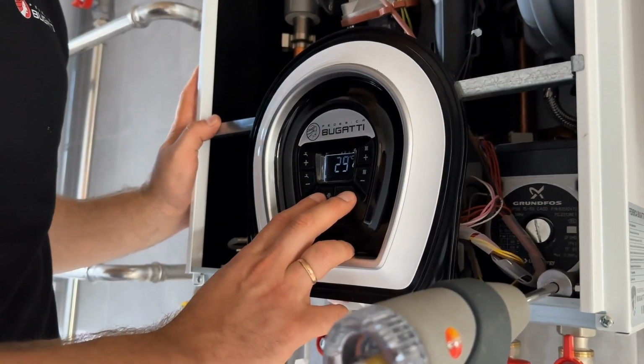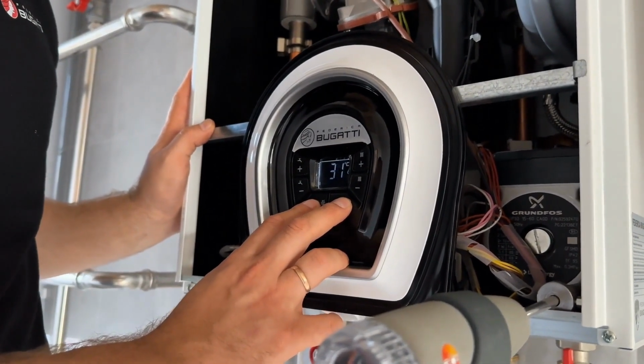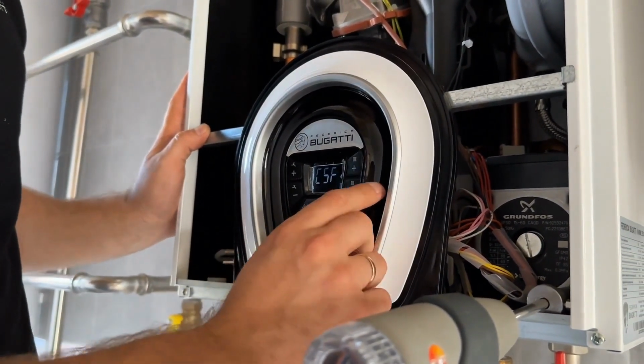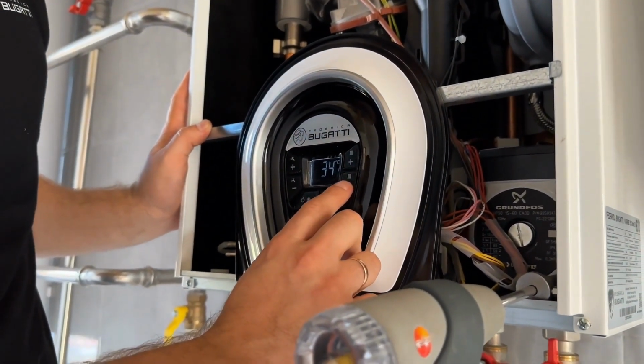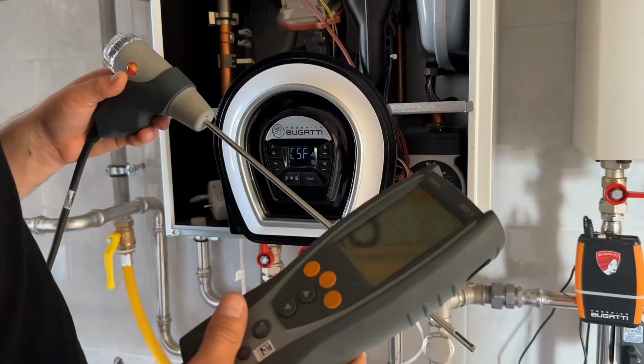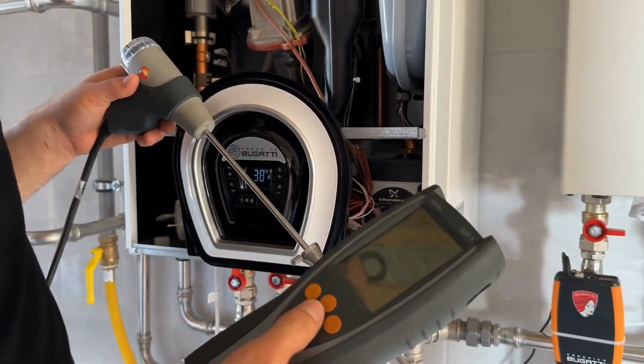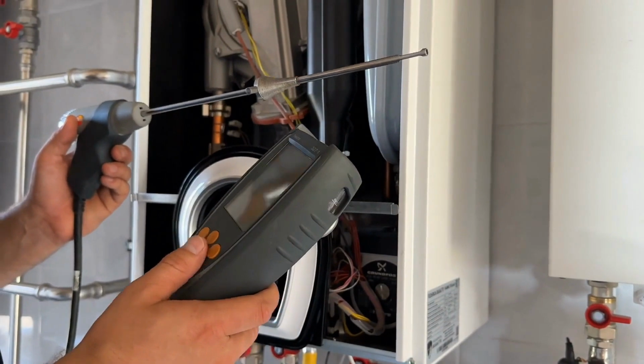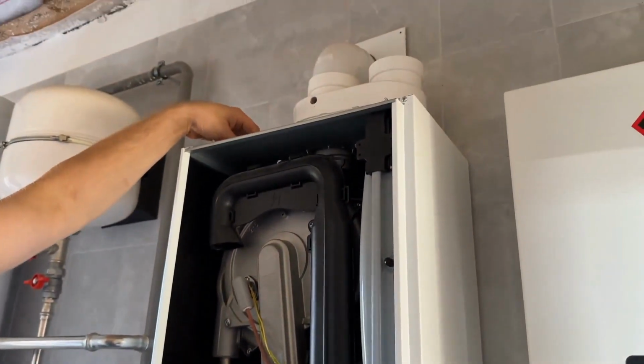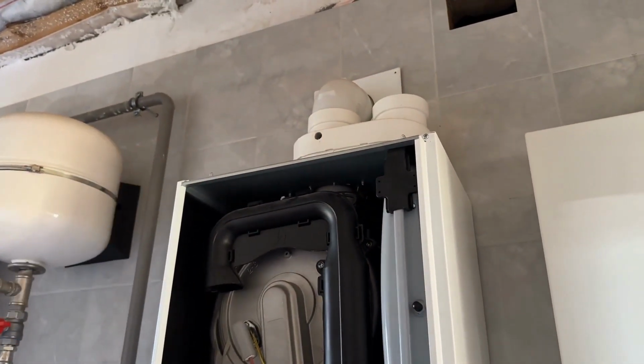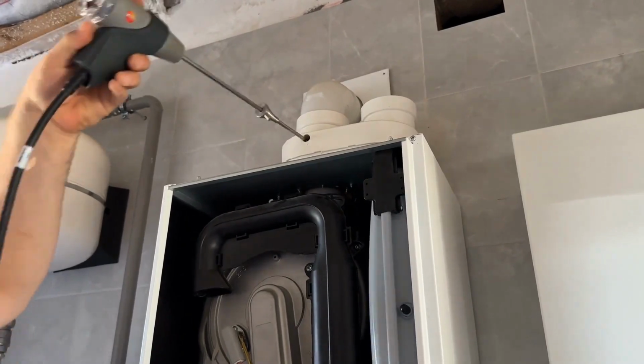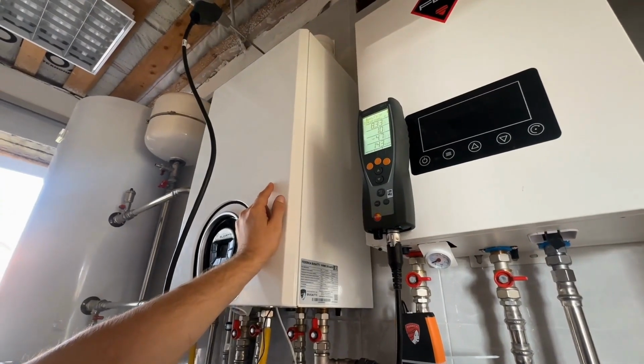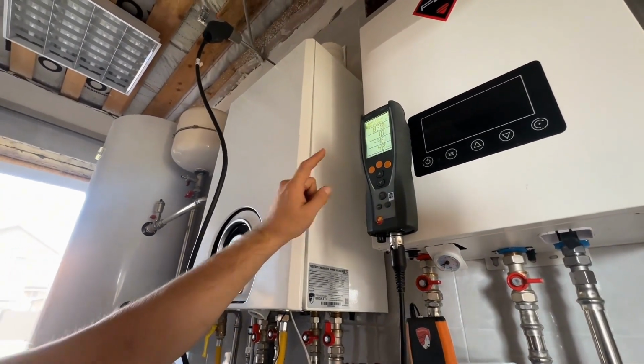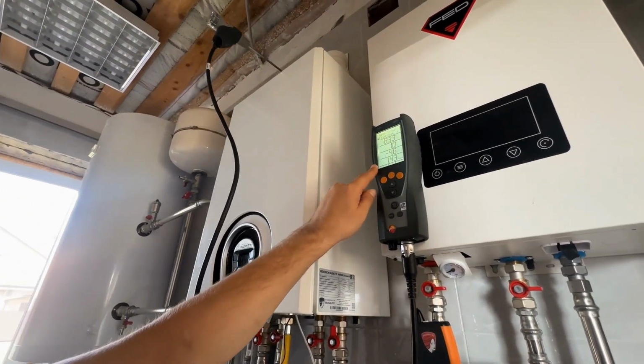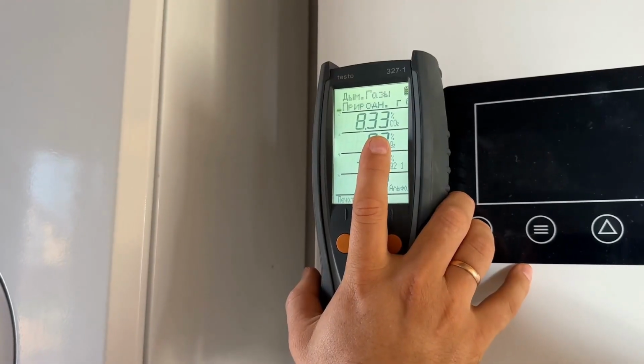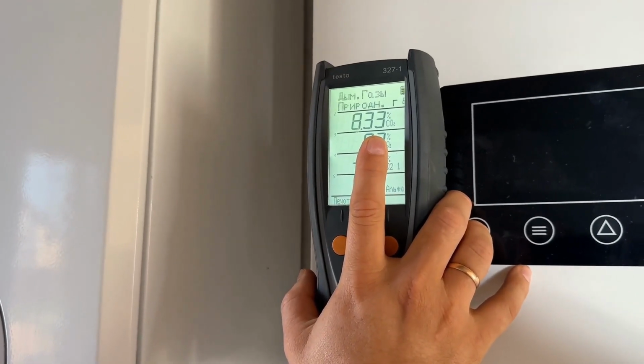To do this, hold down the reset button and the boiler power switch at the same time. To switch to minimum power, we press the heating minus button. Then we proceed to measure the composition of the exhaust gases. For this, we will naturally need a gas analyzer. We unscrew the cap of the sampling probe and insert the probe. The measurement is carried out with the combustion chamber cover closed, and we must wait at least 1 minute for reliable results. At minimum power, CO2 should be 7.8%.